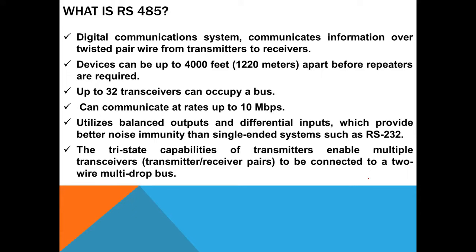There are a lot of benefits behind this module. The main points are: it provides a digital communication system that communicates information over twisted pair wire, and this twisted pair wire can go for a very long distance — up to one thousand meters, which is more than one kilometer. It can also support up to 32 transceivers, meaning more than 32 nodes. Beyond 32 nodes you may need a repeater. For now we talk about only two points — point-to-point.